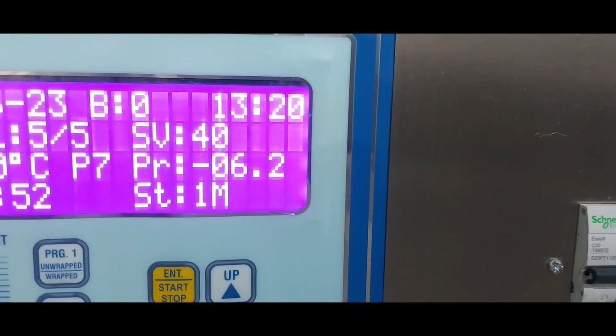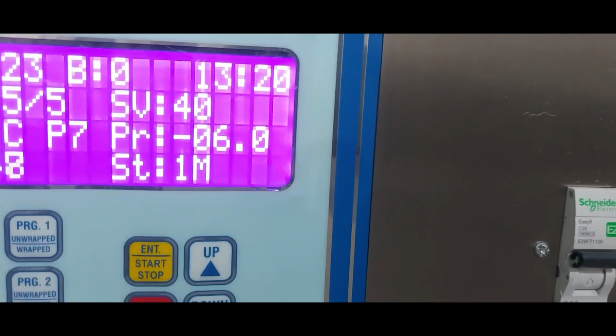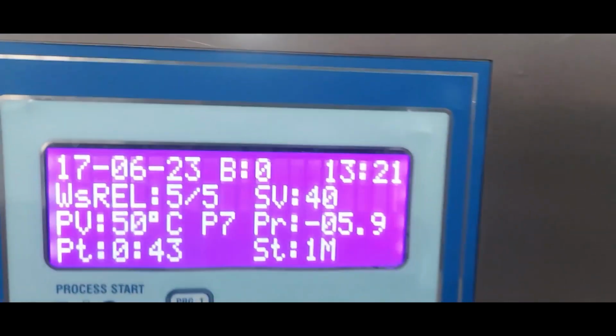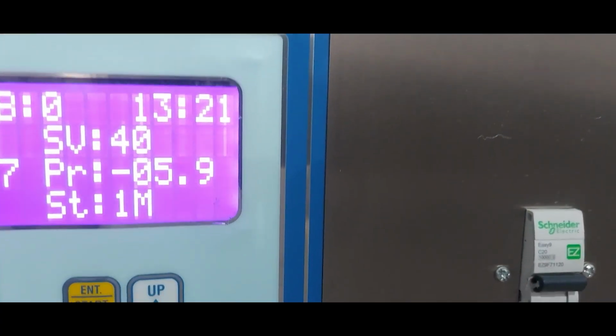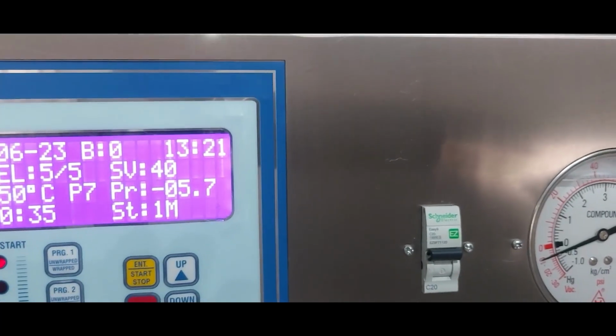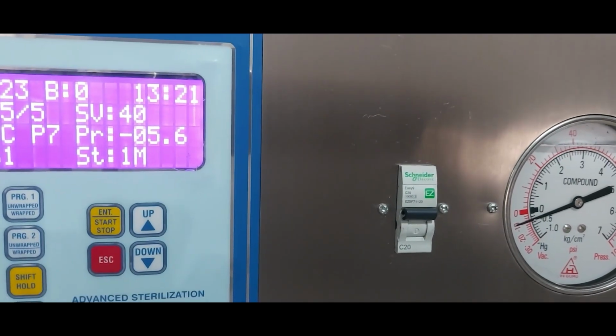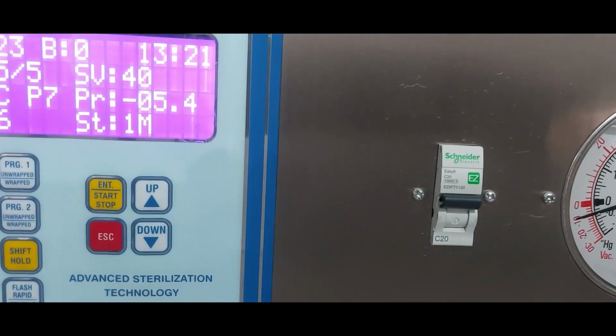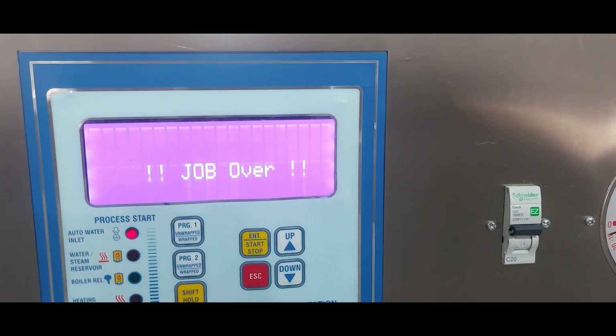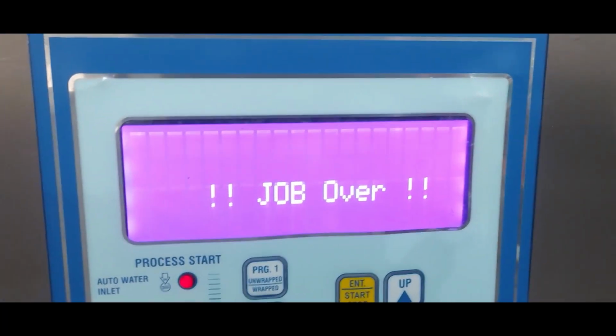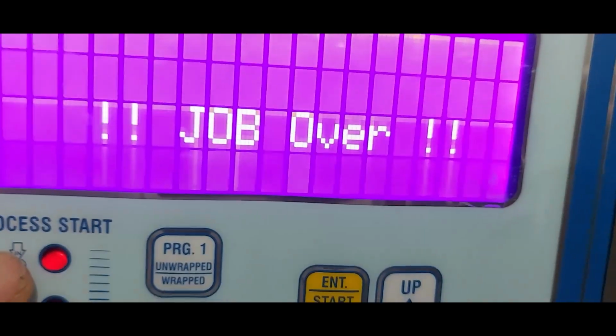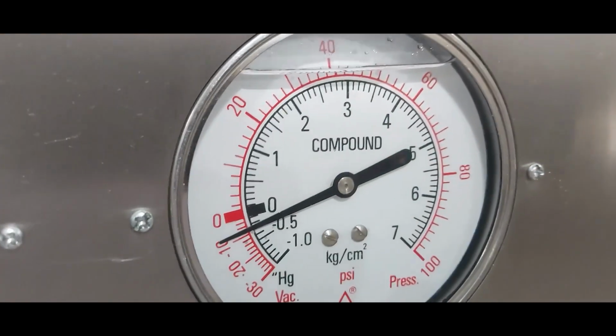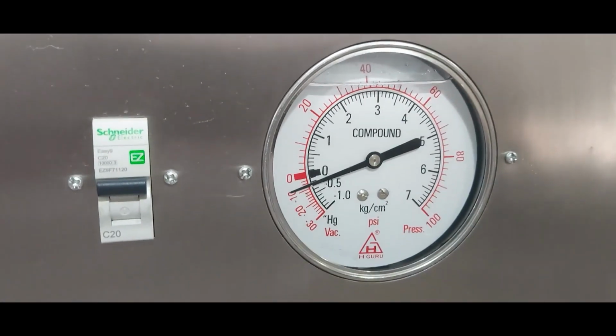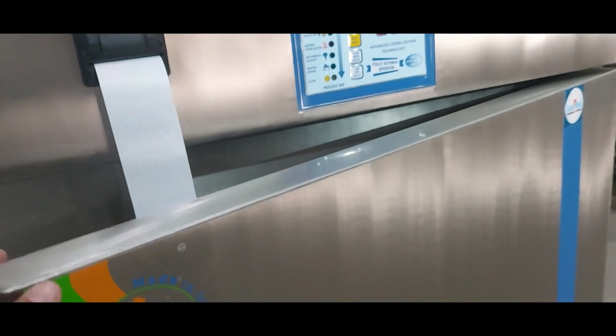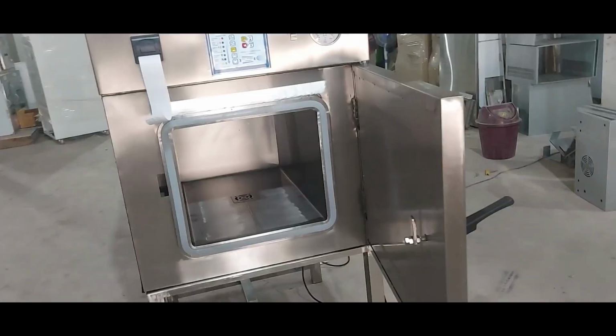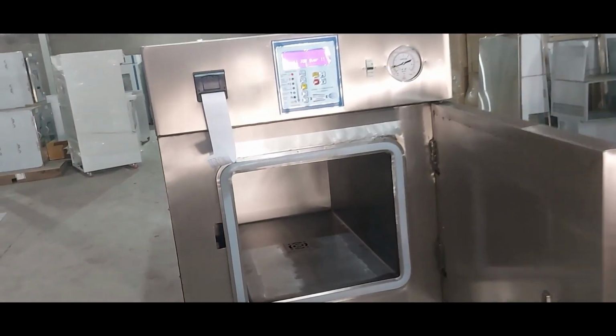At the end, all the air inlet is directly from the HEPA filter, to get only clean air into the chamber during the release cycles. The HEPA filter is made in India only, and this is a very robust product that gives you a very long life, and it is also very easy to replace the HEPA filter from the chamber. The release system is on indicator, and the job is over. The vacuum will slowly go to the 0 level to enable us to open the door. At the end of the process, I'll just open the door. It's a dry run cycle to show you the whole feature of the product.